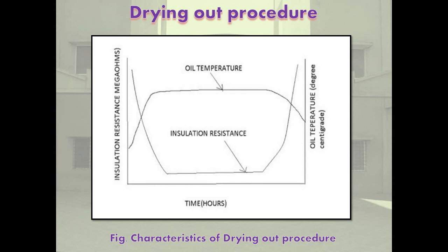In the first procedure of drying out, heat is applied gradually. In this characteristic, this is the insulation resistance in megohm, this is oil temperature in degrees centigrade, and this is time. First the heat is applied, meaning the oil temperature level is high, for example 30 degrees, 50 degrees, 60 degrees, 100 degrees. Heat is applied gradually by one of the above methods to maintain a steady temperature of the winding and oil of the following values: top oil temperature not to exceed 85 degrees Celsius, winding temperature not to exceed 95 degrees Celsius.